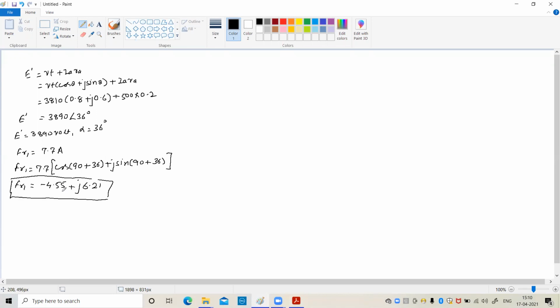Now point number 3 is to calculate FA plus FAL. What is FA plus FAL? FA plus FAL is nothing but the field current or field MMF required to circulate full load armature current under short circuit condition.